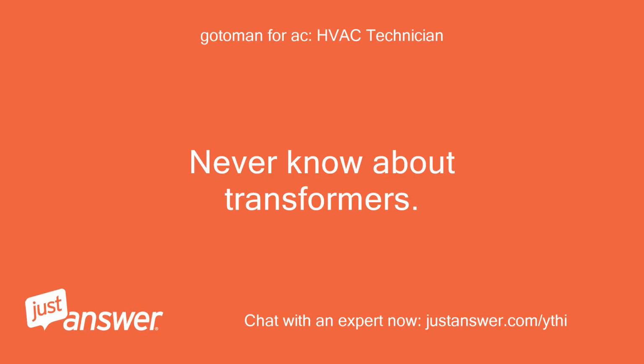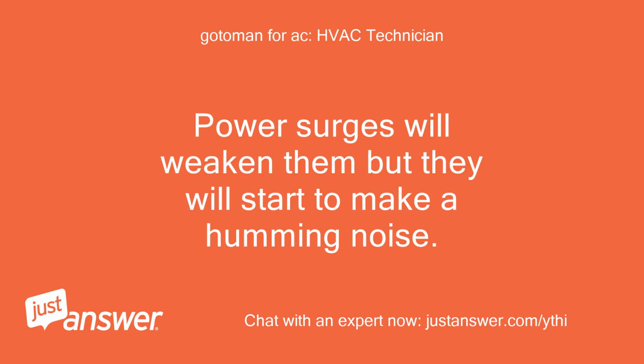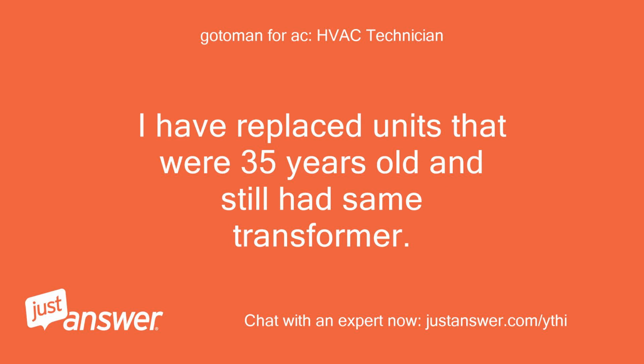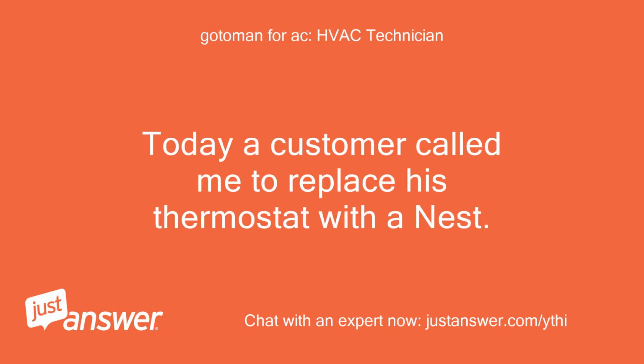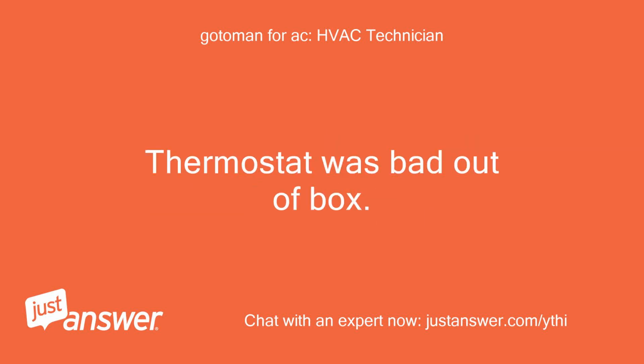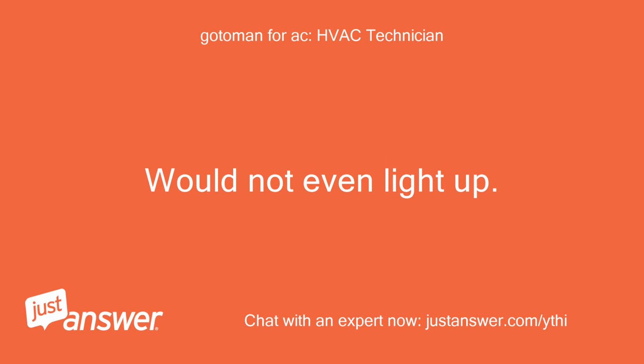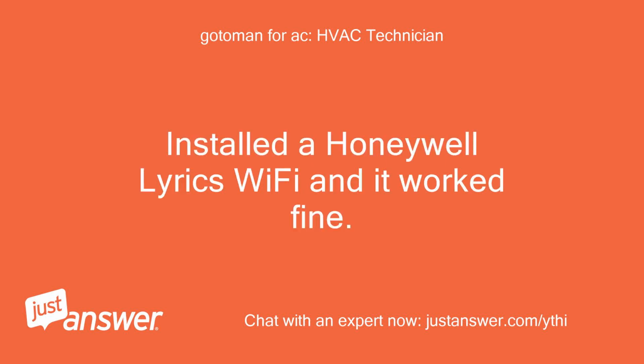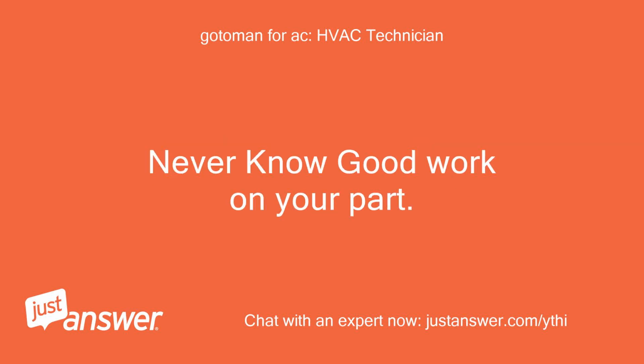Never know about transformers. Power surges will weaken them, but they will start to make a humming noise. I have replaced units that were 35 years old and still had same transformer. Today a customer called me to replace his thermostat with a Nest. Thermostat was bad out of box. Would not even light up. Installed a Honeywell Lyric Wi-Fi and it worked fine. Never know. Good work on your part.